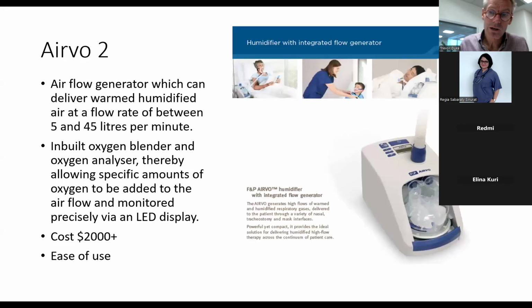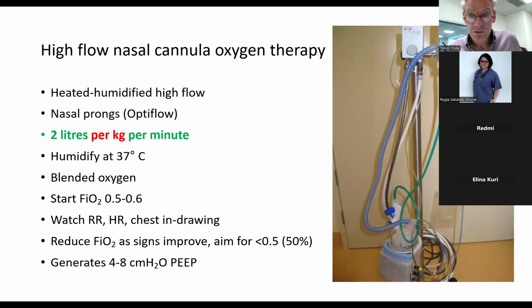I said that there's another device that can give high flow. I won't talk too much about this because there's only a few of these, I think, in PNG. They're quite good compact devices. They have a gas flow generator. They have an inbuilt humidifier. They can give a flow rate between 5 and 45 liters per minute, and they have an inbuilt blender and an oxygen analyzer that tells you just what the fraction that you're giving is. And they cost about $2,000. So they're not cheap, but they are quite effective. They need obviously electricity to run them, but they're quite useful. They also run off those OptiFlow prongs that I talked about before, but that's called the Airvo. But the alternative is to use this type. This is the Fisher and Paykel one, which is a bit more available.